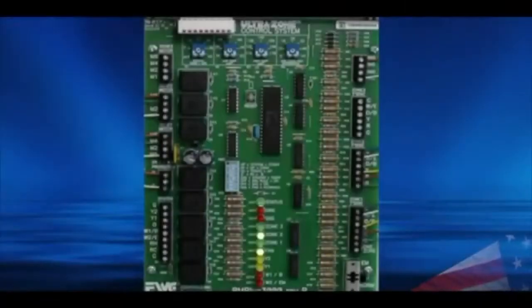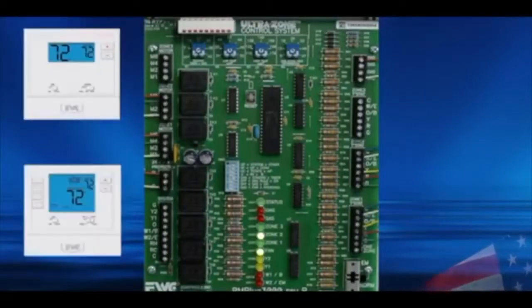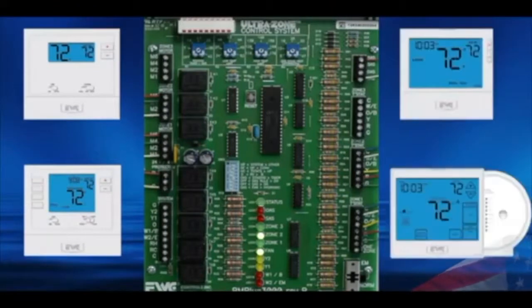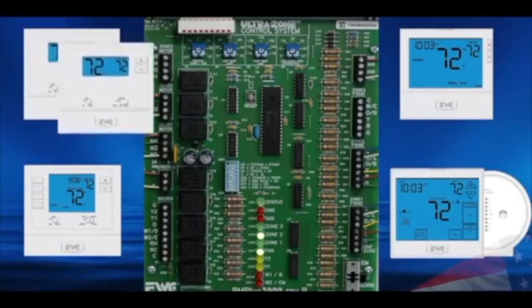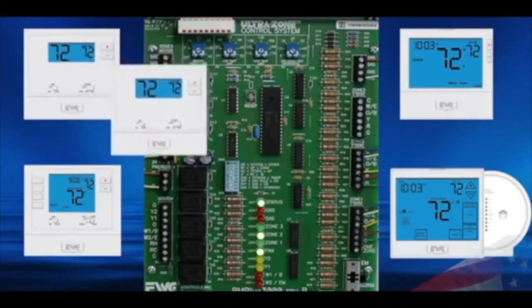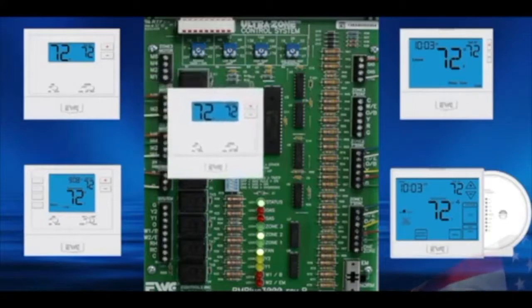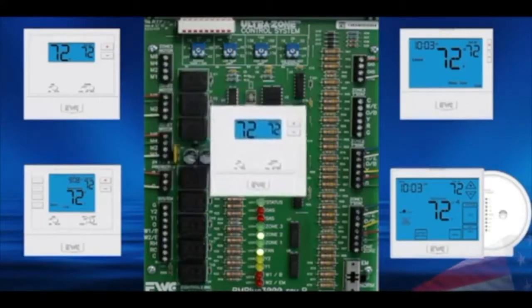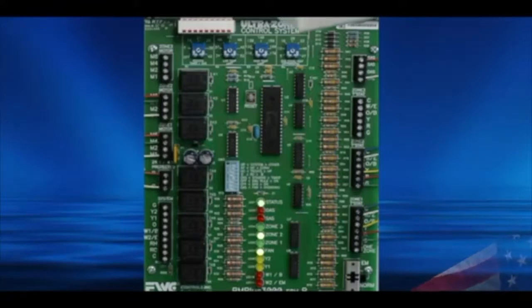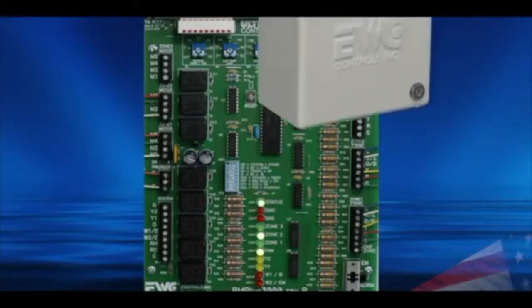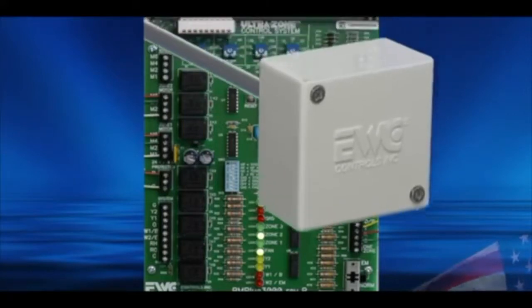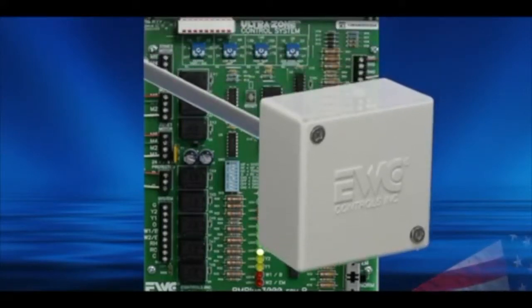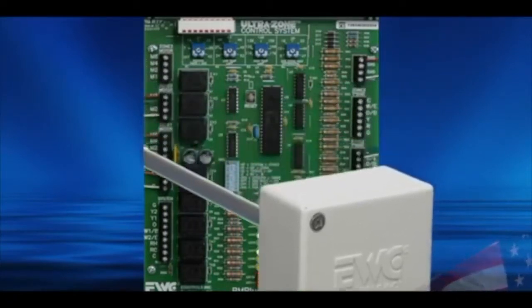The BMPlus 3000 can use any type of thermostat to control zones. You can use hardwired, power stealing, Wi-Fi, or wireless thermostats, any manufacturer. A single-stage heat-cool thermostat can operate multi-stage heat pump and dual fuel systems. You can also use heat pump thermostats, 2 heat, 1 cool if you choose. A supply air sensor, SAS, which has cooling limits and 2-stage heating limits, is included with every panel. This is not an option. It protects the equipment from overcooling and overheating the system.